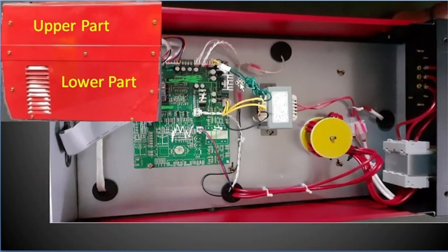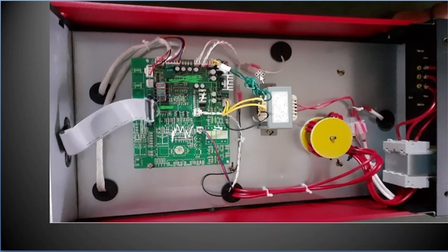The machine is divided into an upper and a lower compartment. We have removed the upper cover. 3-phase input power is coming from this terminal. From here, lines are going to the MCB input. 2 lines of the 3 phases are going to the fan.